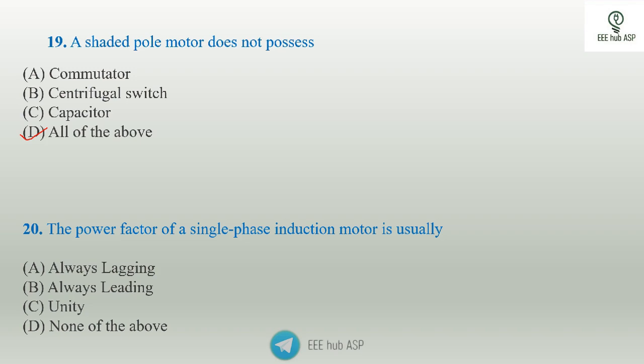The power factor of a single phase induction motor is always lagging under all loading conditions. At full load the power factor is approximately 0.6 to 0.8 lagging. At no load the power factor is very low.